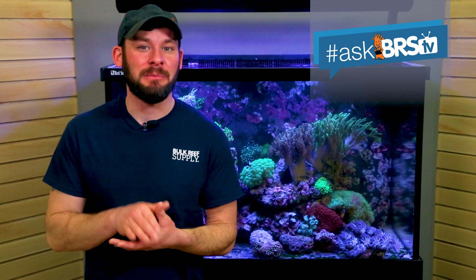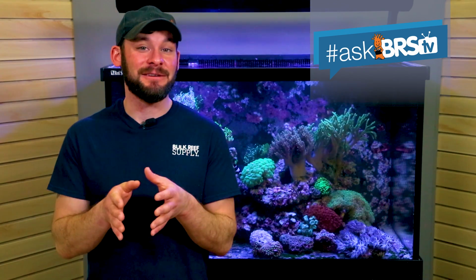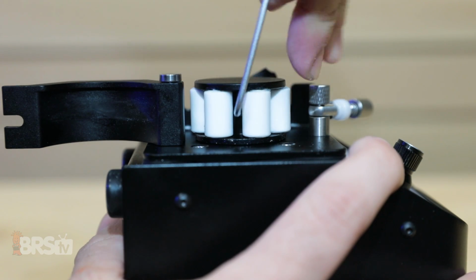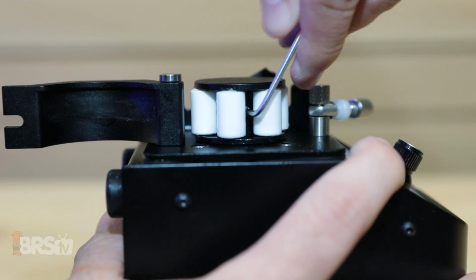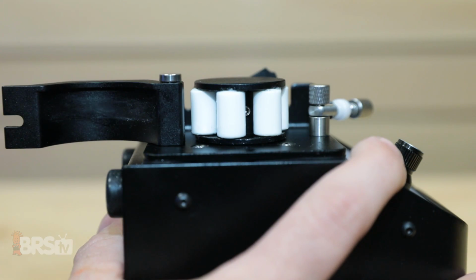You'll want to be sure to tighten the screw down on the flat part of the pump shaft so that it secures the head in place. For me, it's just easiest to remember to face the flat part straight upwards and then tighten the retaining screw accordingly.